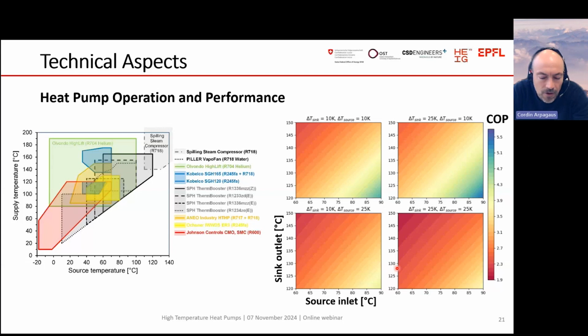So first of all, the technical aspect. We know after some time of analysis what would be a possible heat source, at what temperature, and at what heat sink. Then we can find a possible operating point and check if some heat pump suppliers can provide such a heat pump in this size and working in this temperature range. So we have operating maps of the heat pumps and check if the heat pump can work, and the COP is determined by these temperature conditions.